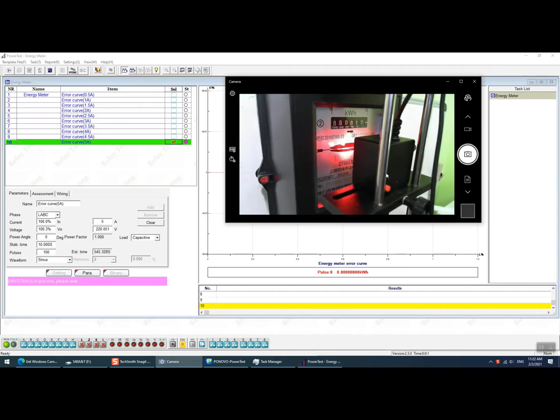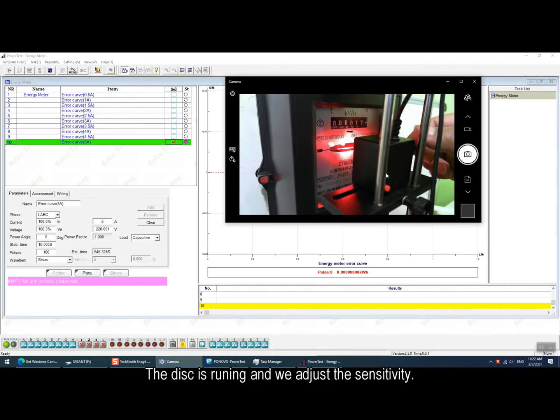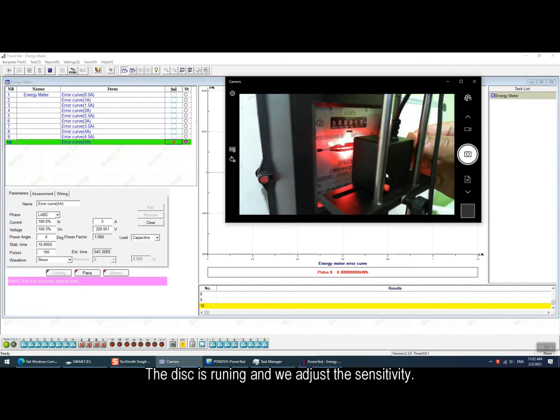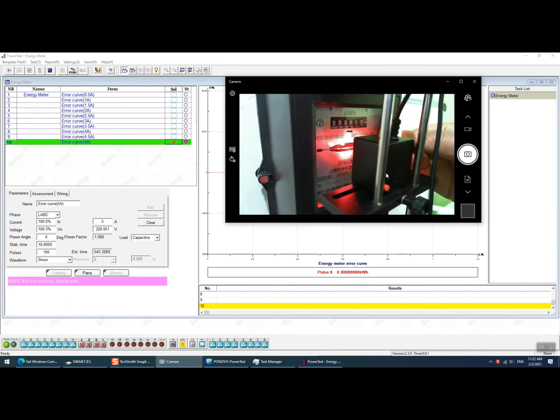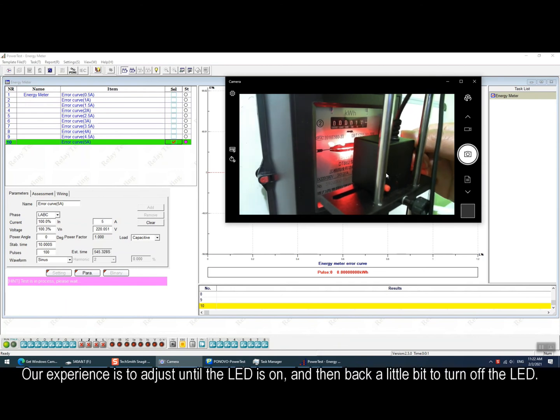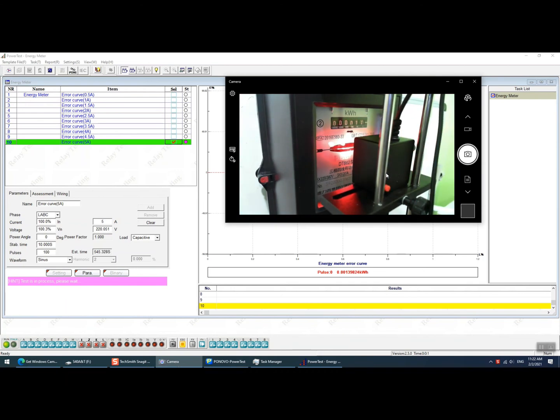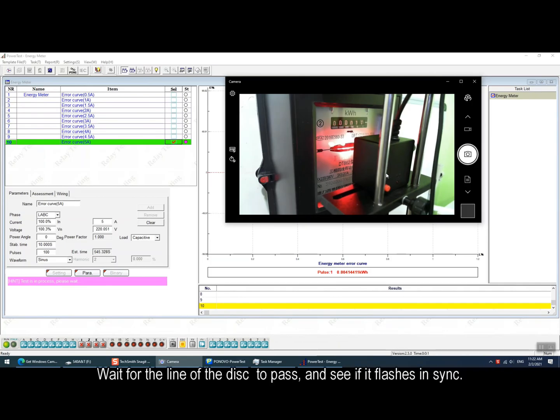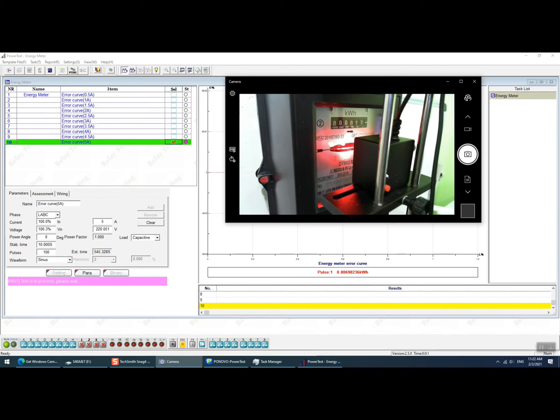And after the injection we can see the disk is running and we can adjust the sensitivity. Our testing experience is to adjust until the LED is on and then back a little bit to turn off the LED.